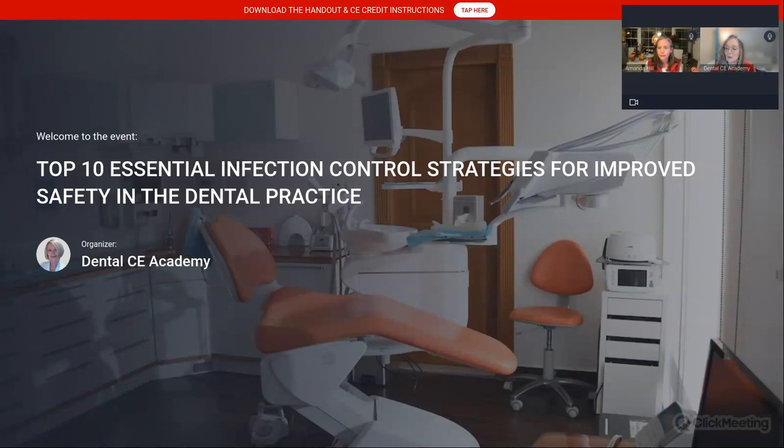Tammy comments that at an office they worked at, they went to take the handpiece off and it was basically calcified onto the line because the previous hygienist never took it off for six years. They had to call Henry Schein to come cut the entire line and change it out. That kind of thing happens, which is why we're all here tonight — and it also happens with suction valves. If you go into your office, you might have to cut the line.